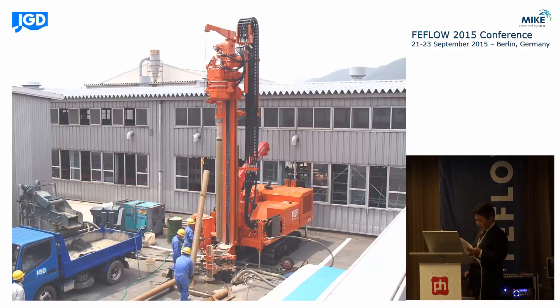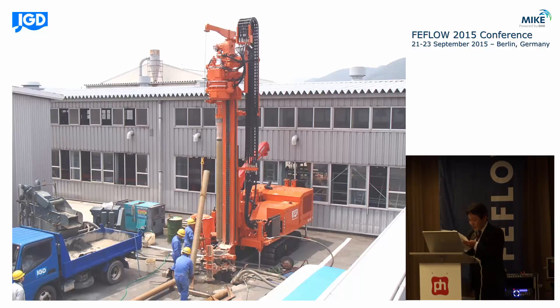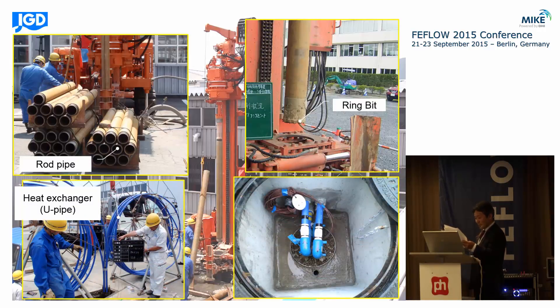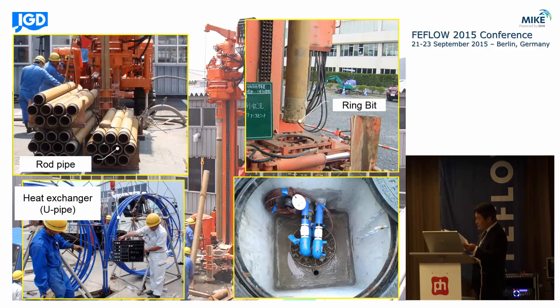In recent years, when digging a vertical type heat exchanger well, a special boring machine is used. Because of the rod pipe, it keeps the borehole wall from collapsing during the boring operation, making mud water unnecessary. However, during the drilling operation, mud in the ground dissolves and becomes mud water. So before installation of the U-tube, washing out is the most important operation. In my presentation, the thermal effects of the mud wall will be evaluated.